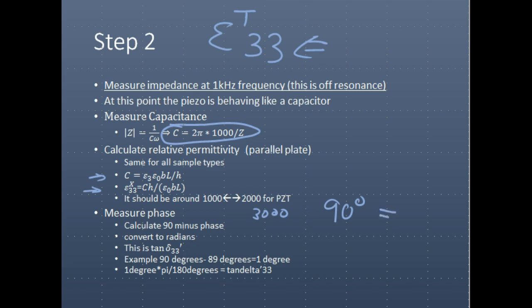But oftentimes, we find less than negative 90 phase. We may find negative 89 or something else. The way you calculate the loss is by this phase value. So 90 degrees minus whatever phase value you got, let's say 89 degrees, you'll get 1 degree.